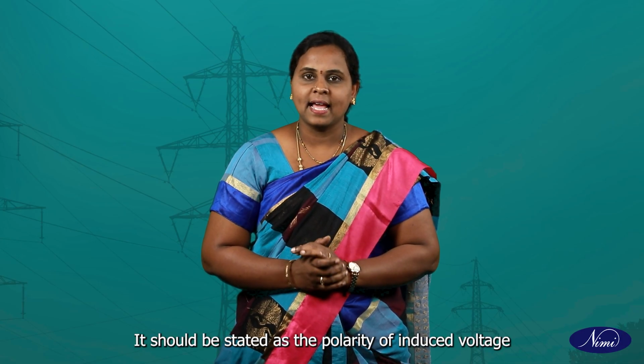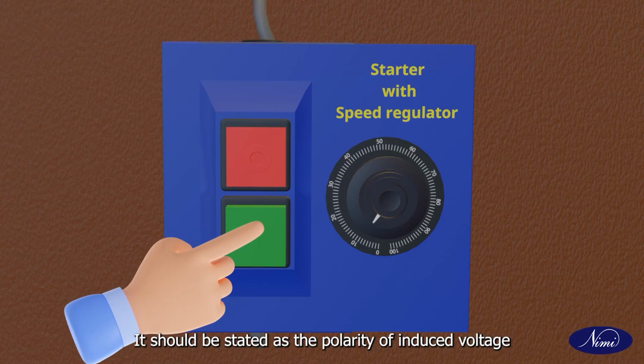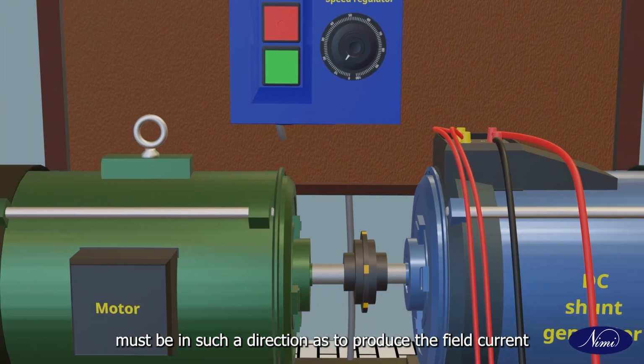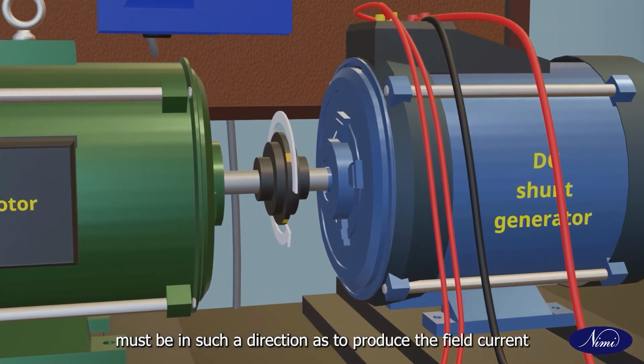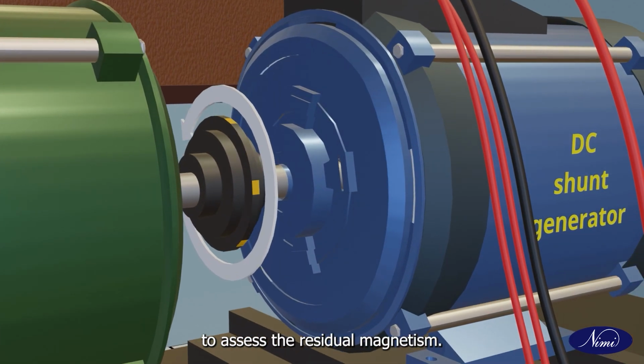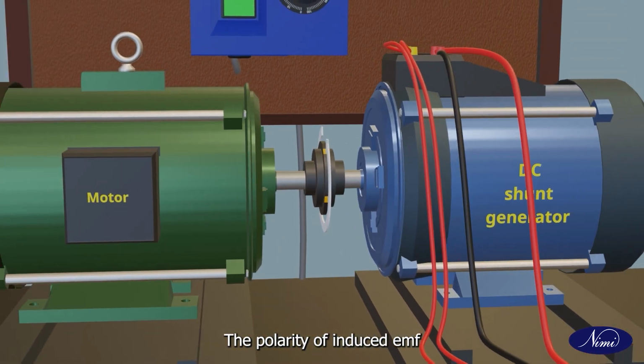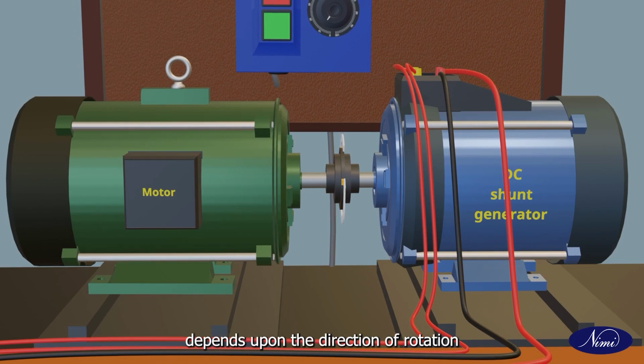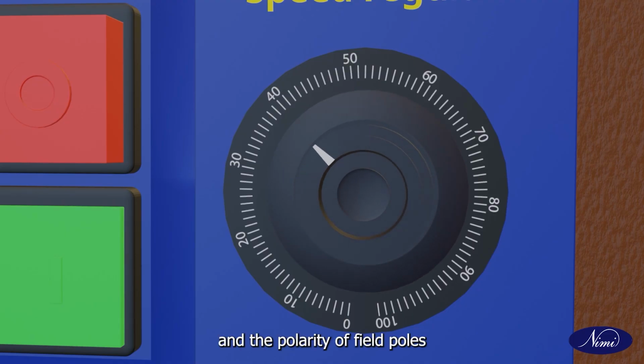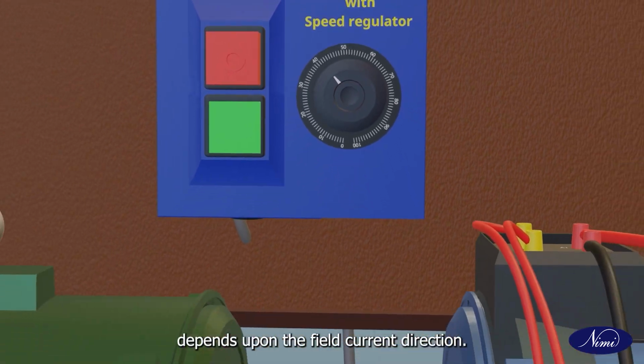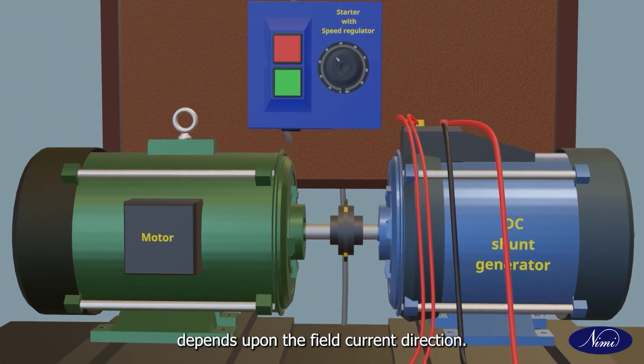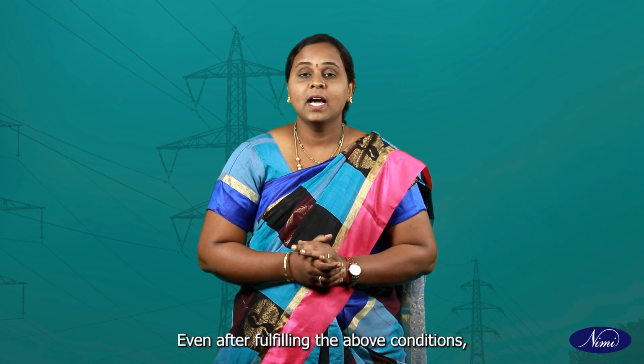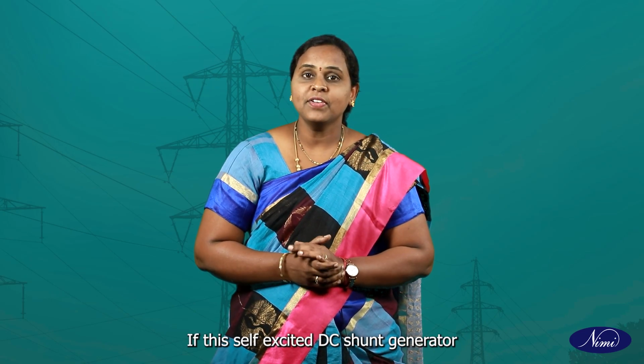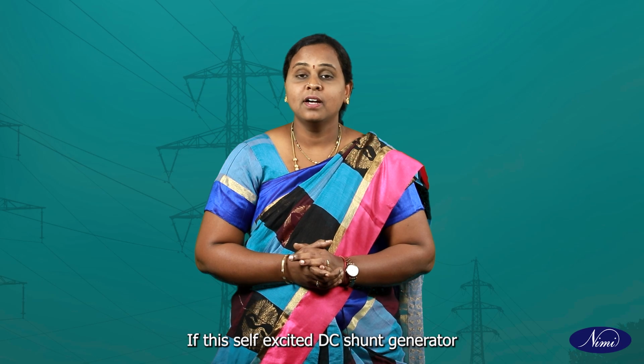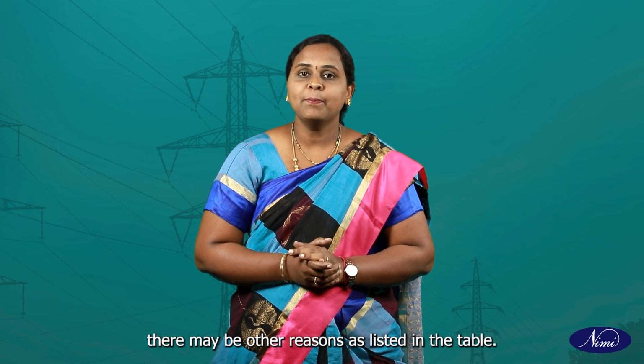There must be a proper relation between the direction of rotation and direction of field current. It should be stated as: the polarity of induced voltage must be in such a direction as to produce the field current to assist the residual magnetism. The polarity of induced EMF depends upon the direction of rotation and the polarity of field poles depends upon the field current direction. Even after fulfilling the above conditions, if the self-excited DC shunt generator fails to build up the voltage, there may be other reasons as listed in the table.